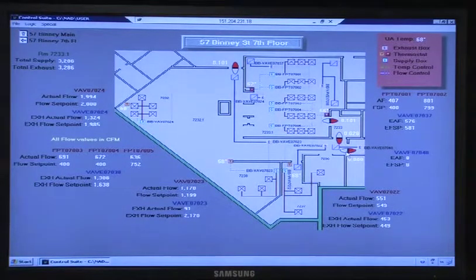Differential flow. Okay. See the balls? You know the little pressure balls, the little pressure transfer balls on the door that run in and out? Yeah, but we're not putting the balls because we're not required to maintain this and this. We want to know what they are for our troubleshooting purposes. We are required by compliance to have a device here and here, and those will be TSI devices with an actual digital readout. You'll see what the differential pressure is, not just a ball.